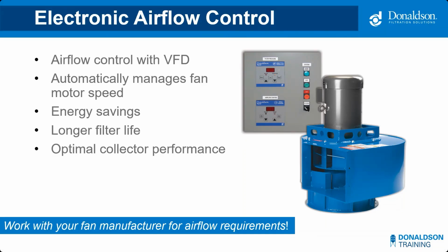We used to only see VFDs specified for larger systems when this type of technology was a little bit newer to the market. But as costs have come down, we're now seeing them specified on even really small systems. If the budget allows for it, this is the way to go, hands down. The lack of manual intervention from operators on the floor will prevent any issues you would have with airflow later on.